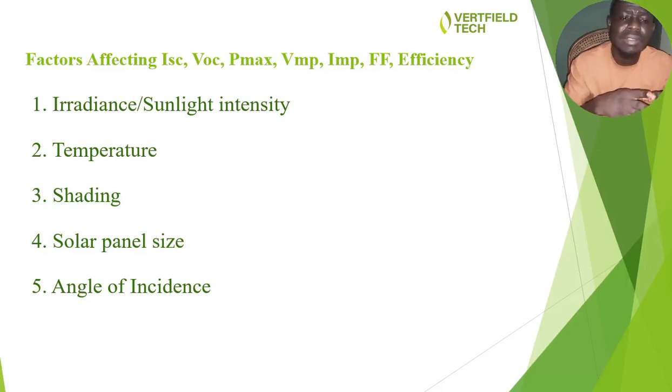Now, we have found out over the years with our experience in the field that some installers who are encouraged by some clients do this funny thing: use a small size of solar panel to power up a facility or recharge a battery. Let's take, for instance, trying to use your 200-watt solar panel to power up your 5 kilowatt hour lithium battery.